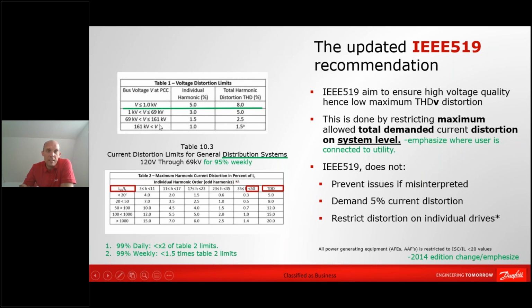As you can also see here, it depends a bit on where you connect. If you are connecting on medium voltage, then you are allowed less distortion. And if you're connecting to high voltage, so now we're talking about 100 kilovolts, then you are allowed even less distortion. The reason is simply that you want less and less distortion the higher in voltage you get, because you are distributing the voltage to more consumers. But for your typical applications where you're connecting to 400 volts or 460 volts, you have to ensure that your distortion level on the voltage is not exceeding 5%.